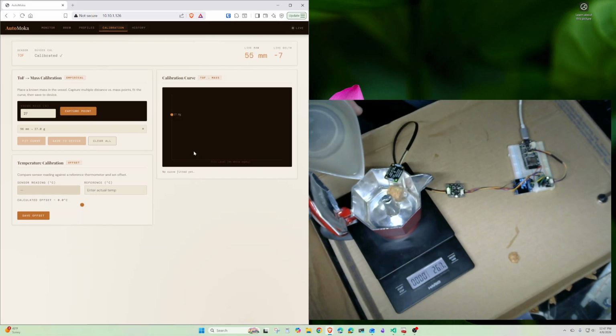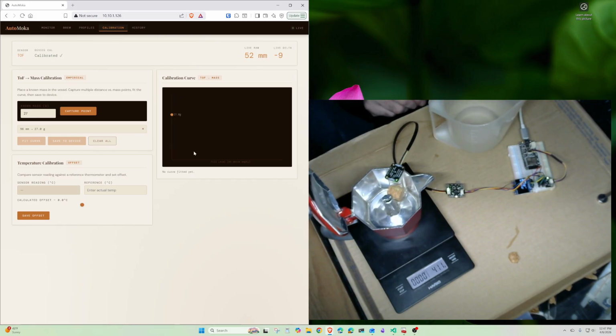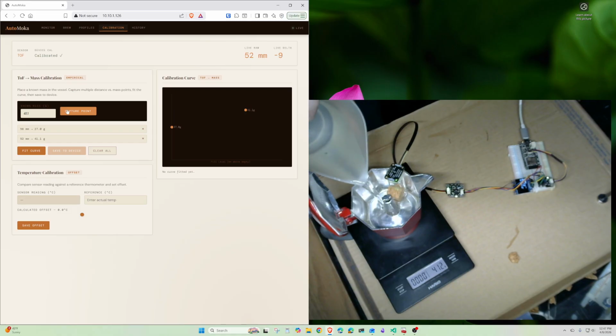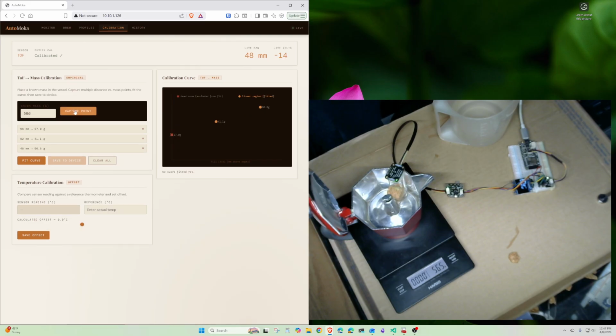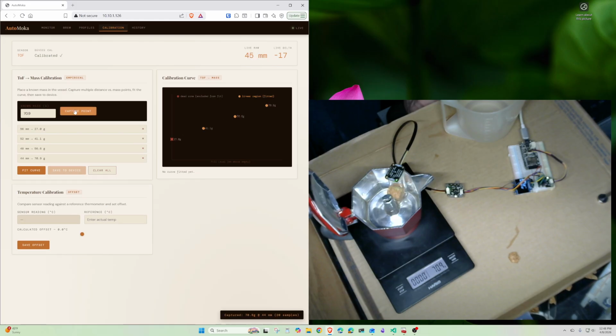Now we will put some more in. It's at 41.1 grams. Capture that point. Let's go some more. 56.6, I think that is. Now this will only have to be done once for a pot. Once we get this calibrated, we won't need to do it anymore. Let's put some more in. What do we add here? 70.9. Capture that point. All right, it's nice that we're getting a nice linear chart here. That's good, because we're going to use that linear line to get our output coffee.